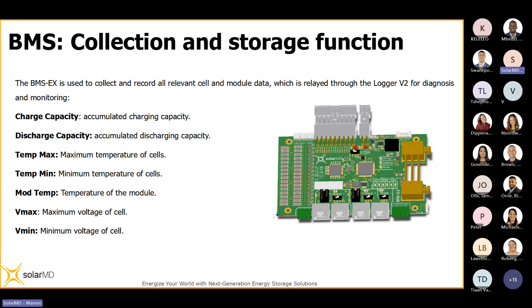So that's a close-up of the battery, looking at some of the key features. As I said, the shunt is on the far right-hand side, CAN bus communication on the bottom. On the far left you're seeing the cell balancing circuits. The balancing method our BMSs use is known as passive balancing - essentially a couple of resistors in series. When one of the cells has a higher voltage above a preset threshold than the rest, that circuit closes and we burn off the excess energy through heat. There's an alternative called active balancing, where power is shifted around between the cells, but that's expensive to produce and more complex, raising the cost of the battery significantly. So that's not really a solution we offer, but passive balancing gets the job done in a cost-effective manner.